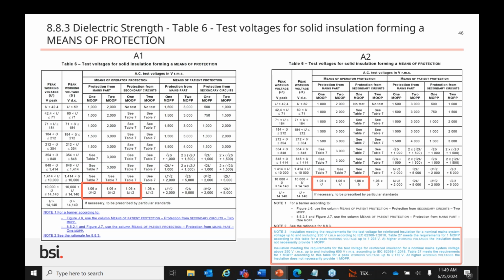Also be aware there's other tables that have been updated. There's table 8, multiplication factors for air clearance for altitudes. There's minor standard reference updates. Table 12, there's minimum creepage distances and air clearances providing means of patient protection. Important details all in the notes. Next slide.